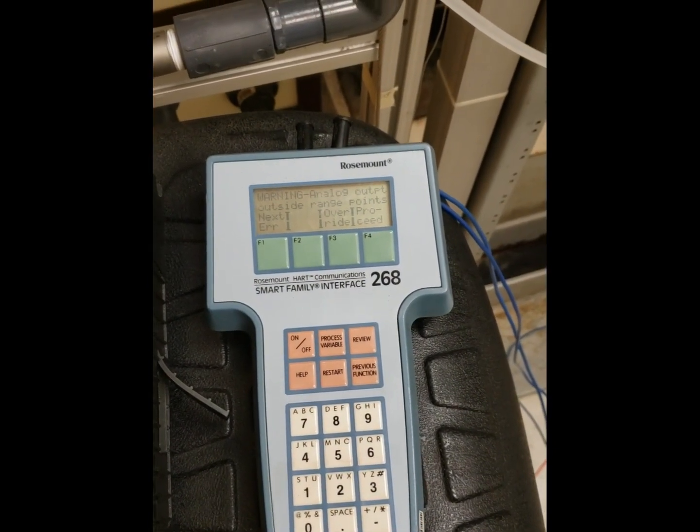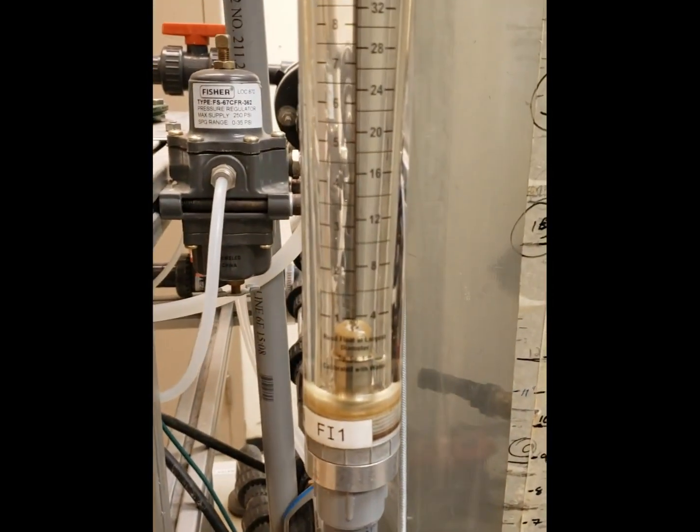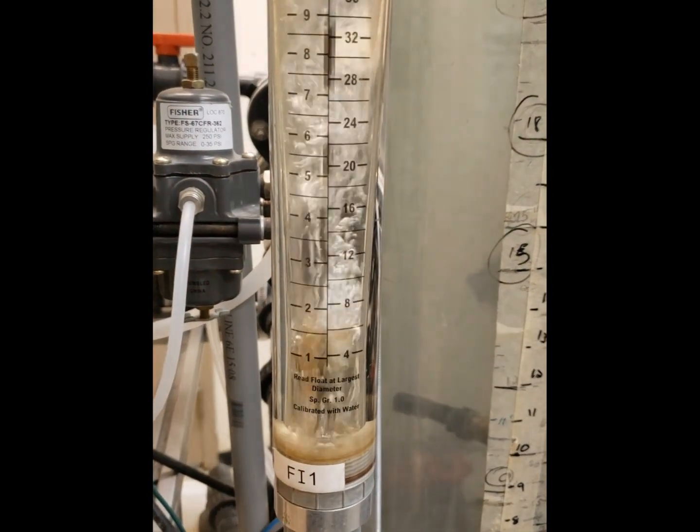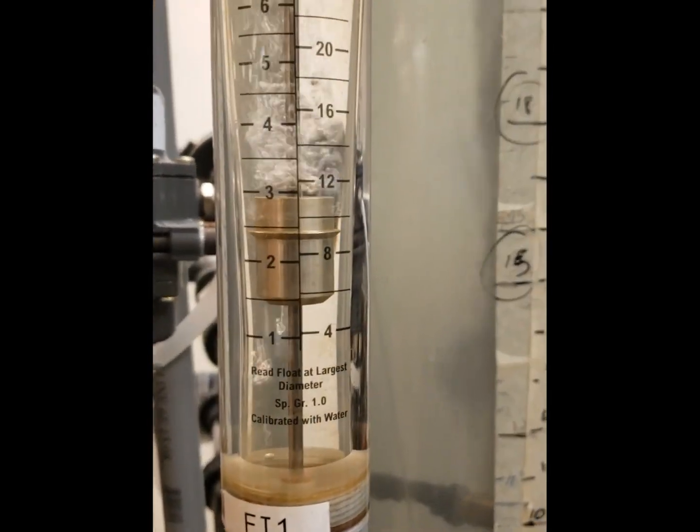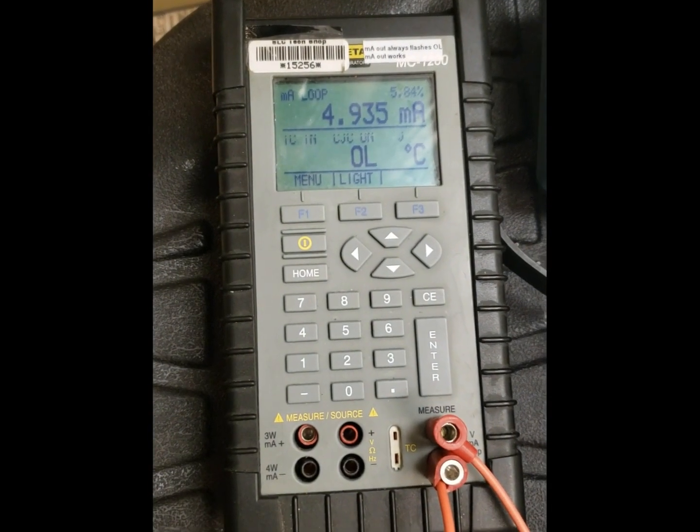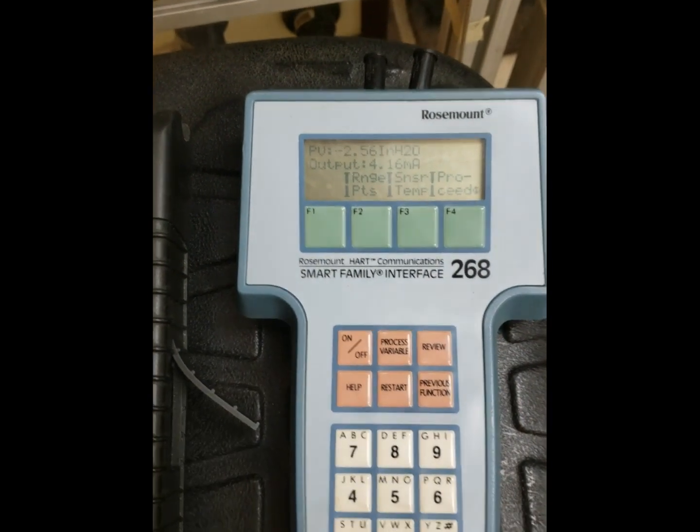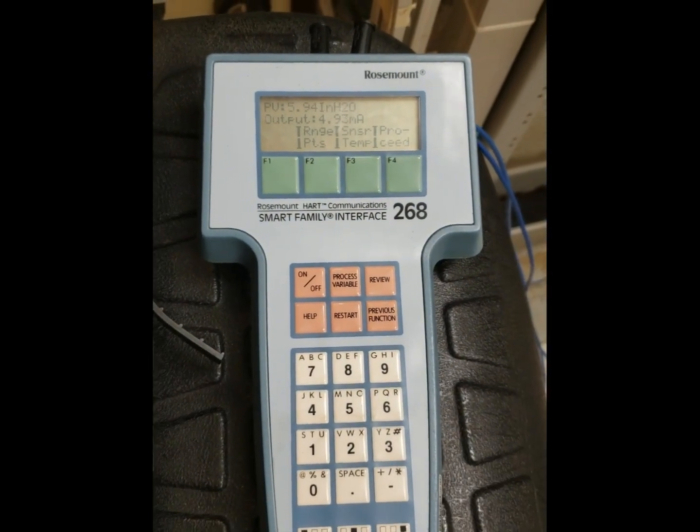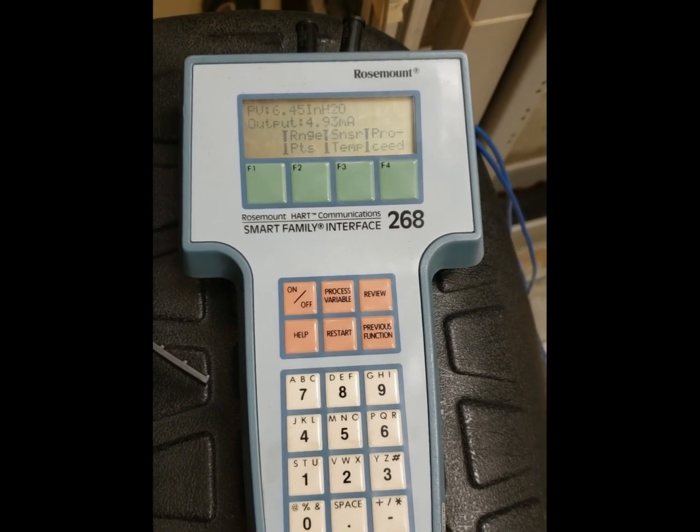So if we take this down to zero flow we have close to four milliamps and our transmitter says it's just outside its own range. So now we're going to put it up to 25% which would be two and a half gallons per minute.